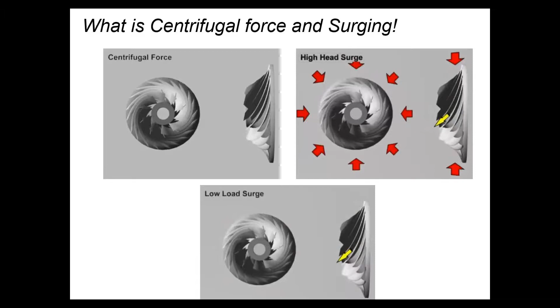And refrigerant is actually flowing back into the compressor again, which is again resulting in stalling of the compressor. At any given point in time, the compressor is trying to pump the refrigerant, and refrigerant is flowing back, and it's trying to stall the compressor. That phenomenon is called surge. And surge is detrimental for a centrifugal chiller. You don't want surge to happen because anything could happen in the compressor. Your compressor motor might burn out, there could be a complete explosion on the inside of your compressor, and your impeller might get broken into pieces. You don't want that to happen.